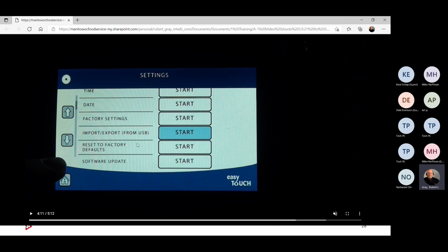So I only use the factory default option if everything else fails and I have no other option but to do that. Keep that in mind. That is my last resort. I don't want to use that unless I absolutely have to, because I know once I push that button to say yes, it's going to come back on. I'm going to have the appropriate software for the UI, because again, it doesn't save software. It goes back to whatever it was before it was out there.